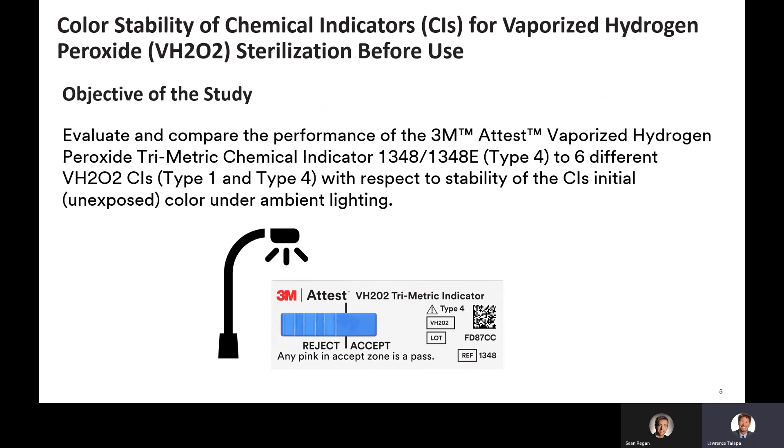The 3M Attest trimetric CI has been categorized by the US FDA as a multi-variable chemical indicator for chemical sterilization, and is labeled as an ISO Type 4 chemical indicator per ISO 11140-1:2014. The 3M Attest trimetric CI also has a kite mark certification from BSI as an ISO Type 4 CI.